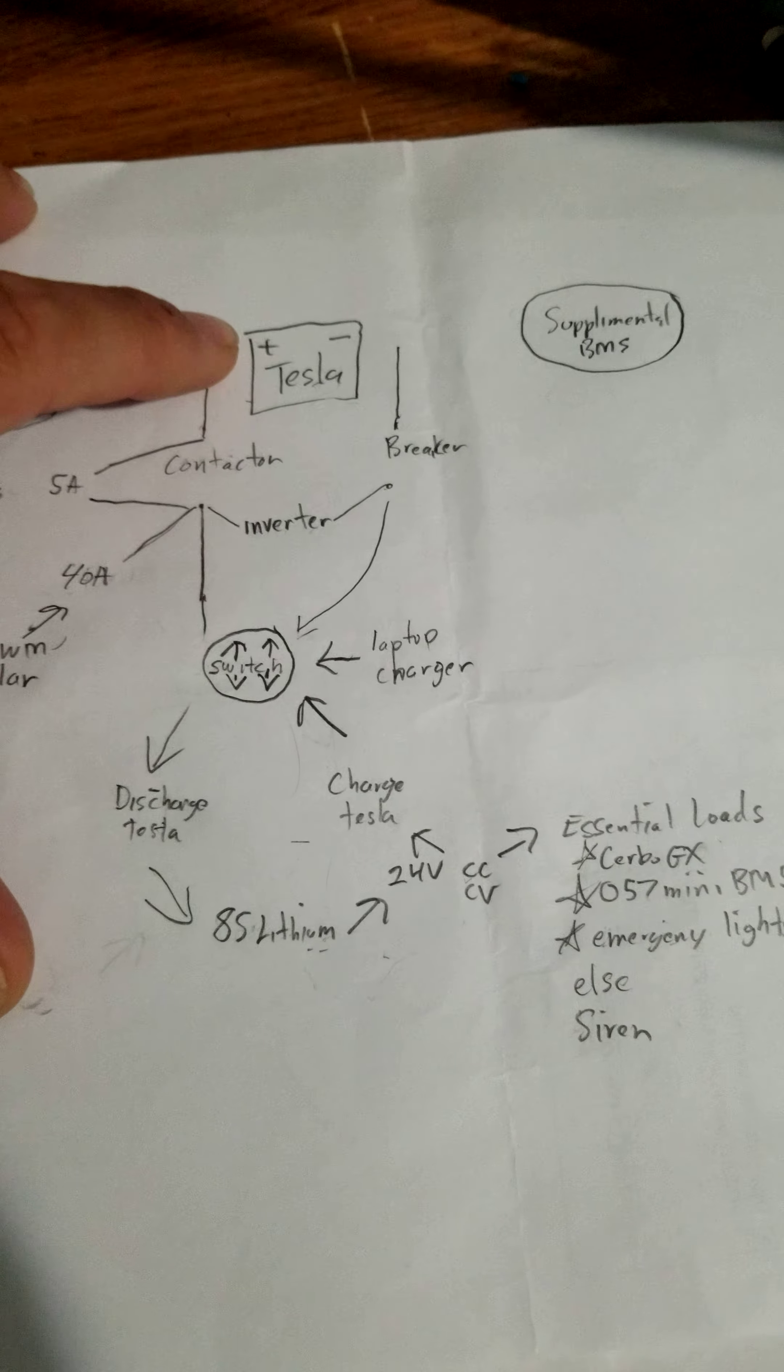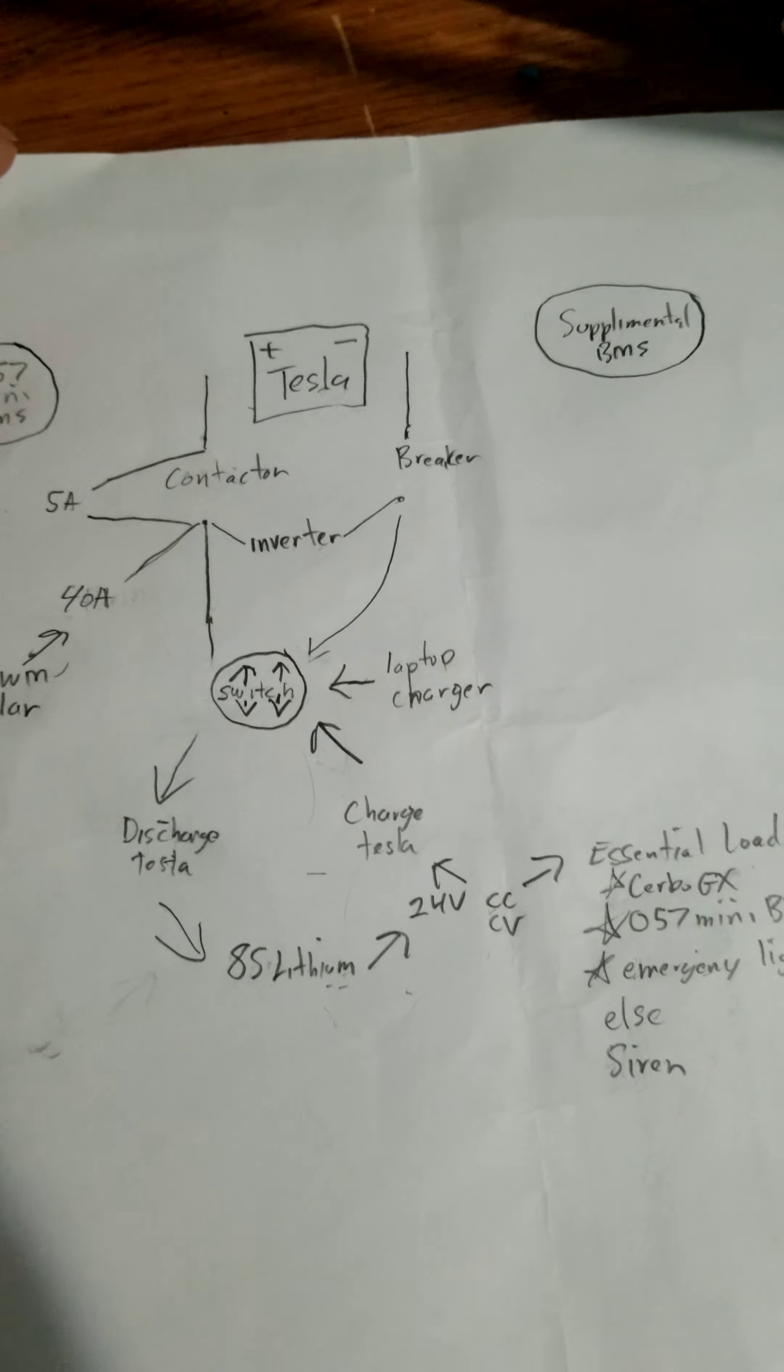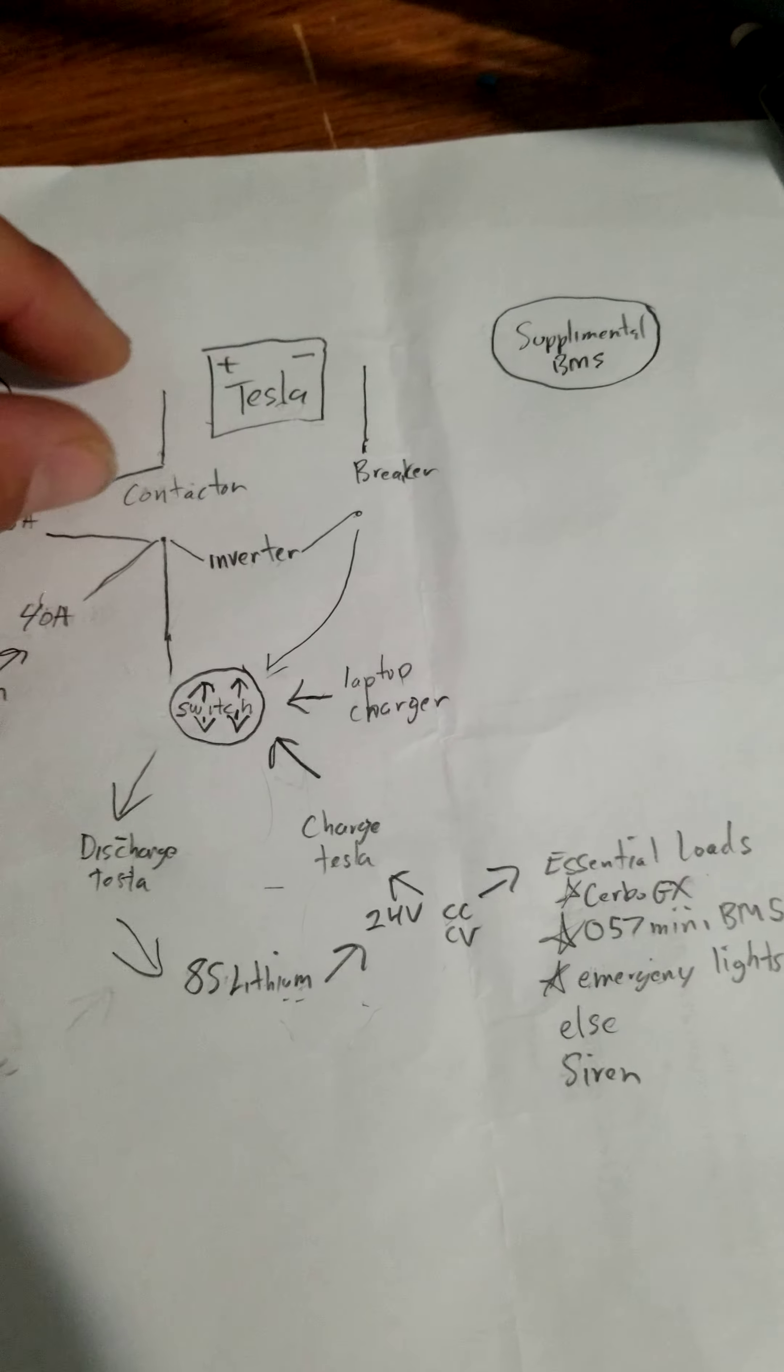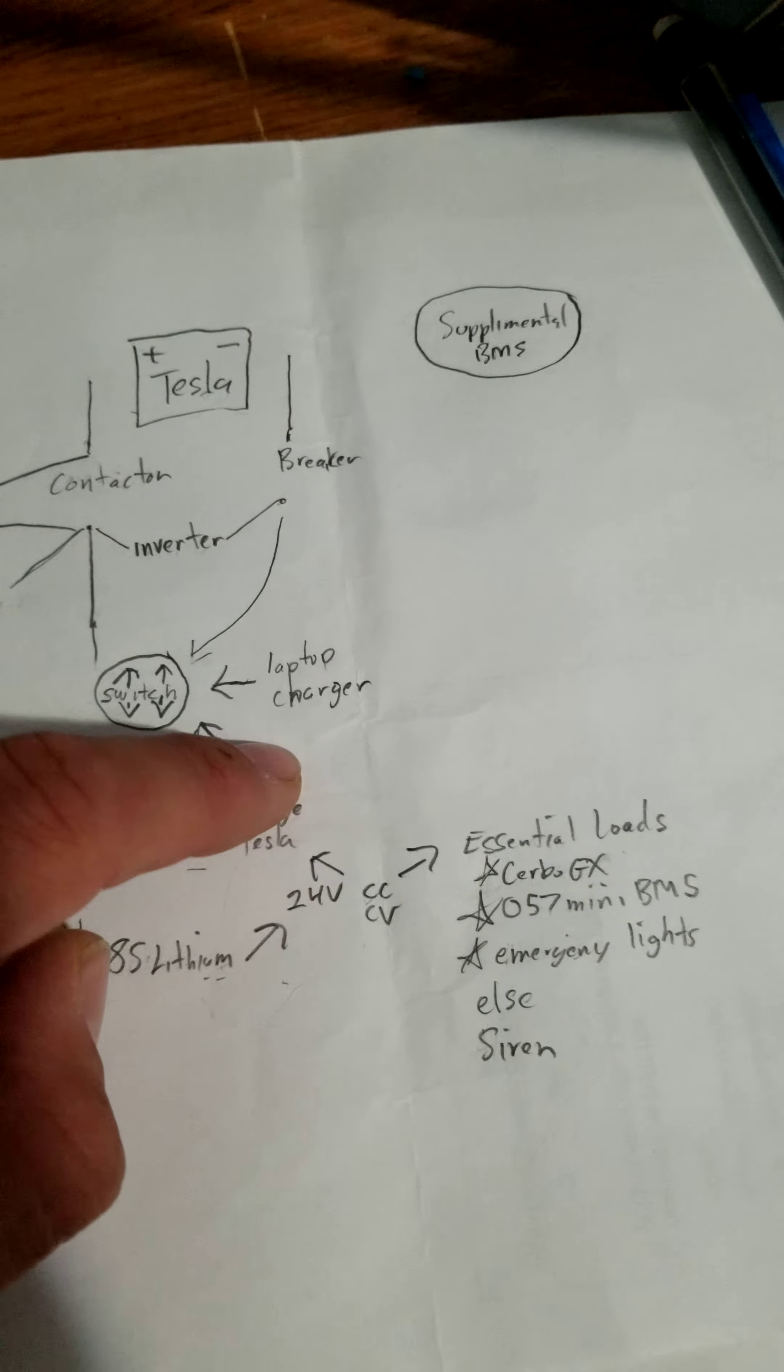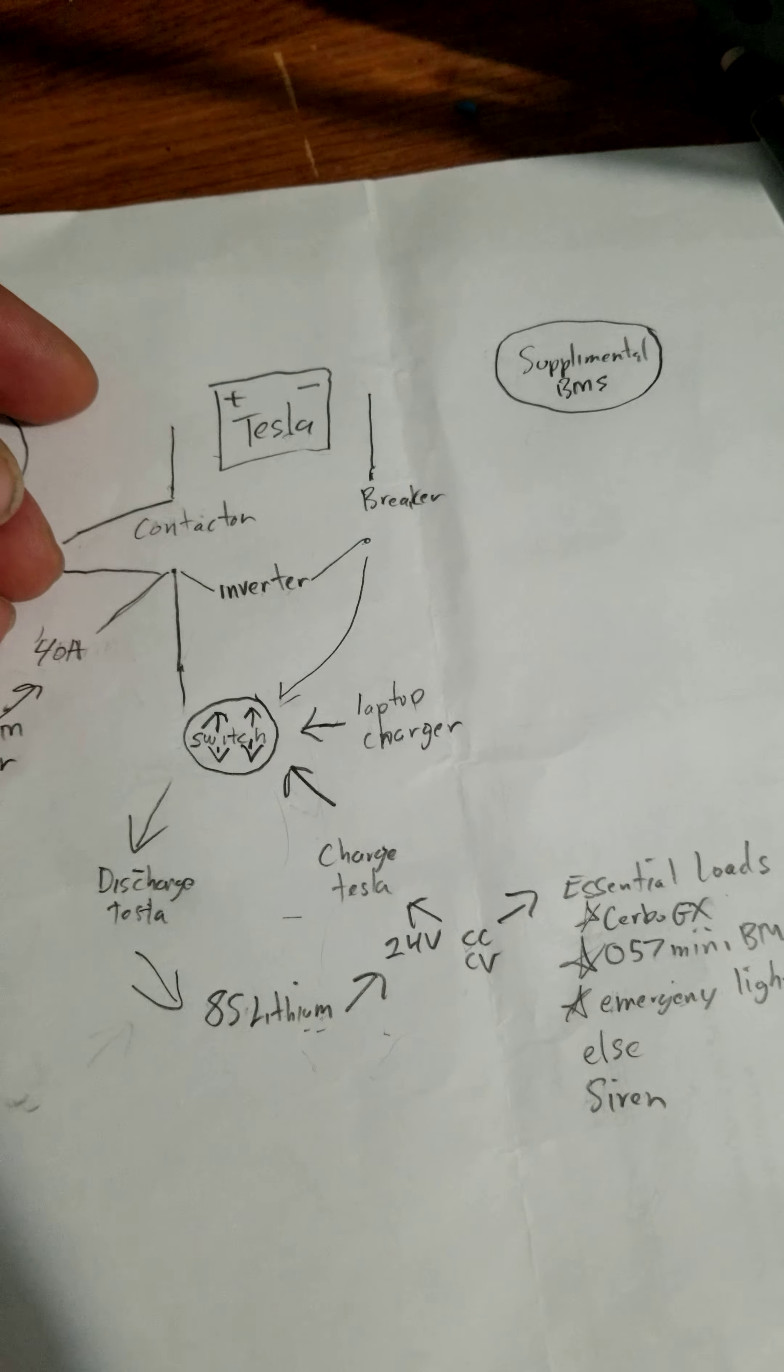This Tesla battery is going to go ahead and shut itself off eventually because even though when one cell drops down it'll shut the contactor off and then it'll auto balance the cells and the contactor will turn back on again and it'll power this essential loads for a little bit and then it'll turn itself back off again.